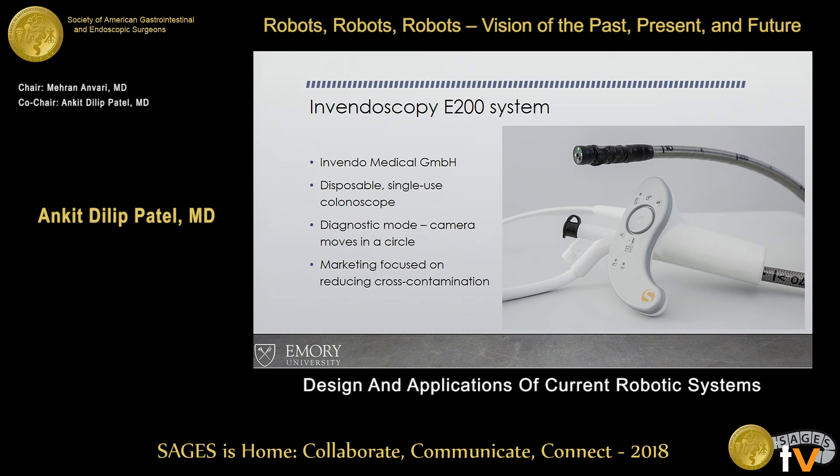The Invendoscopy E200 system, available in Germany, hasn't been widely adopted here in the U.S. It's a disposable single-use colonoscope — the handle is reusable but the scope itself is disposable. As the endoscopist is pulling back, you can enter a diagnostic mode where the camera automatically moves in 360-degree rotation, recording all the pictures so you can go back and review them later, lowering the chance of missing anything. The marketing focus is on reducing cross-contamination risk.